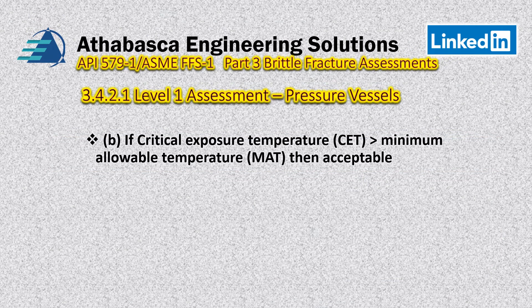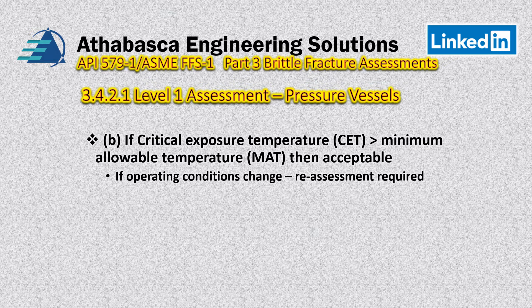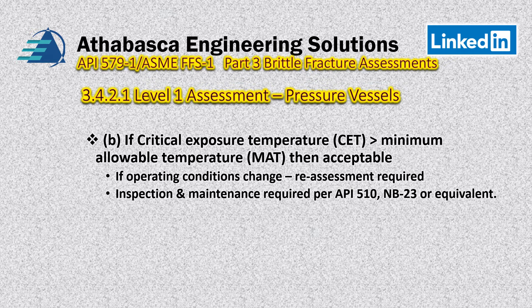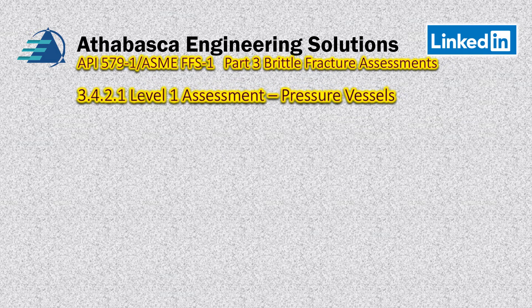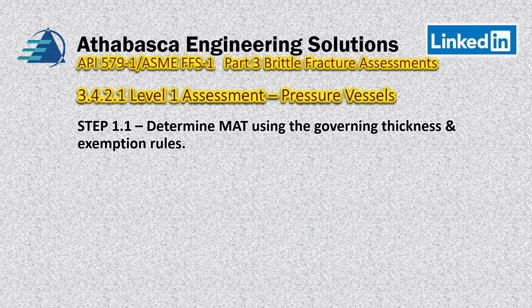As a reminder, as we've talked about in earlier episodes about minimum design metal temperature, the critical exposure temperature outlined by the process must be greater than the minimum allowable temperature, the MAT. For it to be acceptable, we use MAT because we're looking at each type of component; we put them all together and that becomes the minimum design metal temperature. So if the operating conditions change, API reminds us that a reassessment is required. The second part is if inspection and maintenance is required per API 510 or NB 23 or an equivalent.